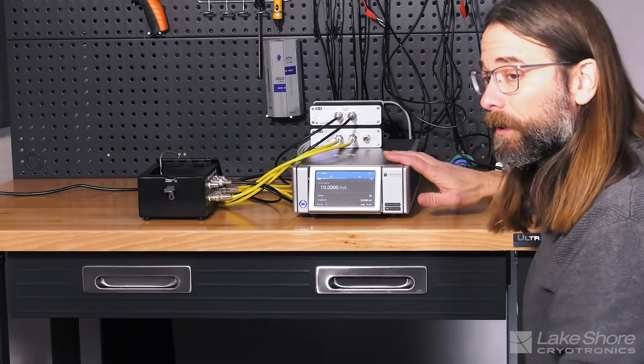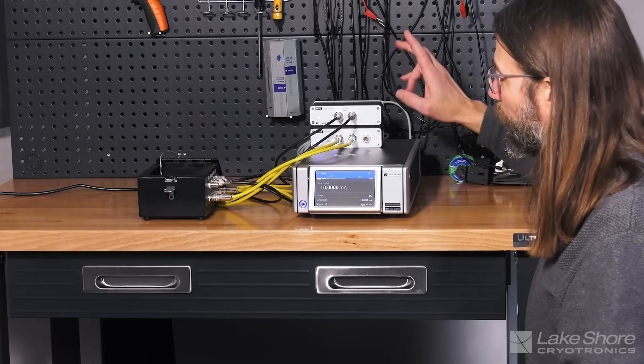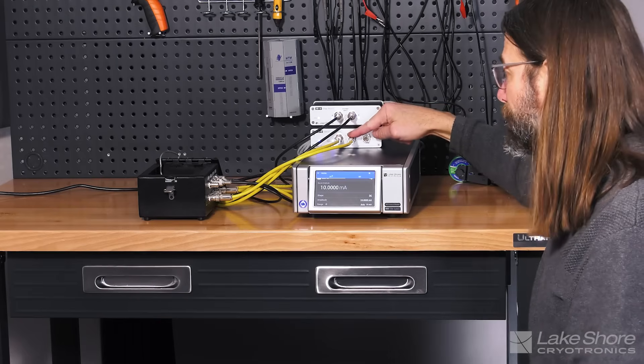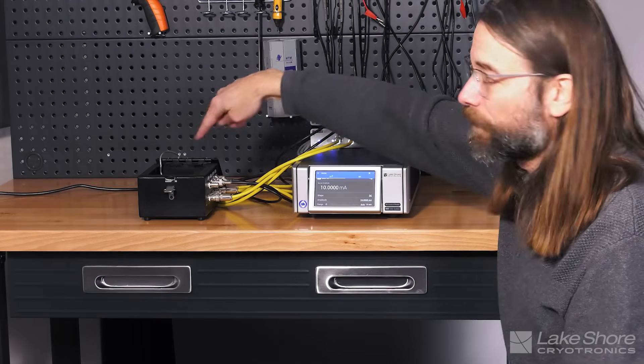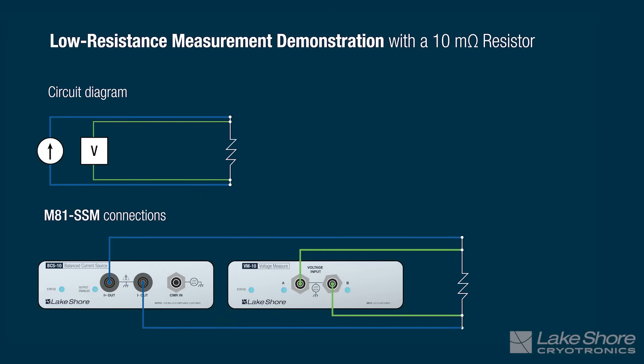It's connected up to our M81, which is our source measure system from Lake Shore Cryotronics. In this case, we are going to be sourcing current. We're using the BCS10, which is our balanced current source, and that's going to be sourcing current through the device under test. And then we're going to be performing a voltage measurement using our VM10 or voltage measurement module.